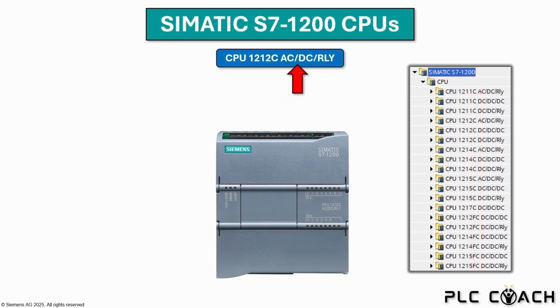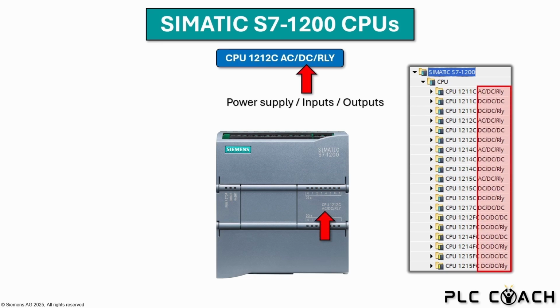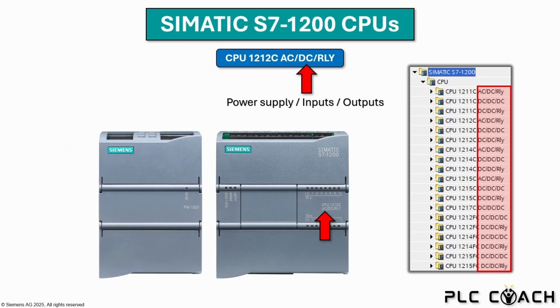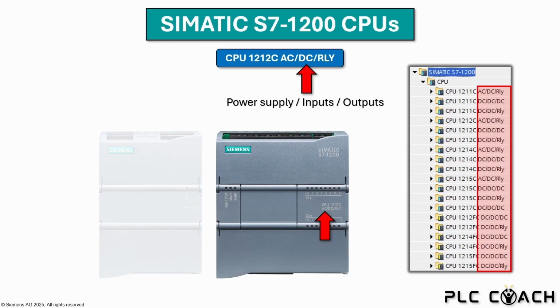The last part indicates the power supply as well as the type of inputs and outputs. An AC CPU has an internal power supply and can be operated, for example, at 230 volt AC. A DC CPU requires an external power supply as it operates on 24 volt DC. An S7-1200 always has DC inputs. This means that they expect a 24 volt DC input signal.